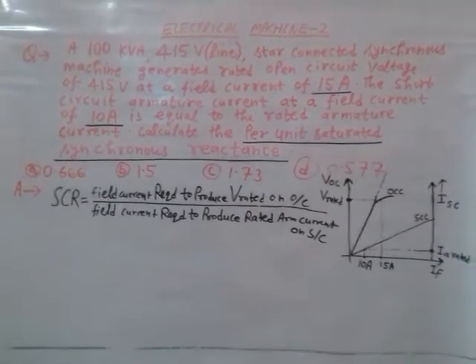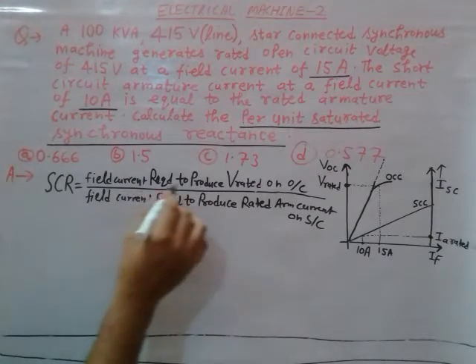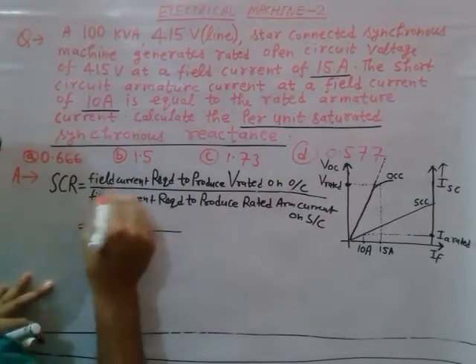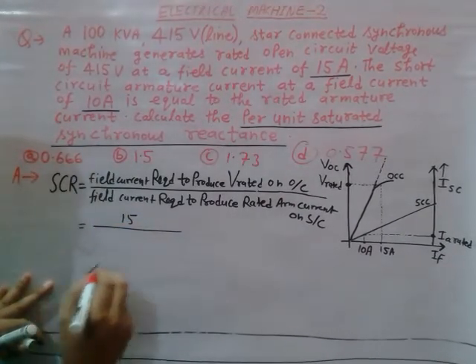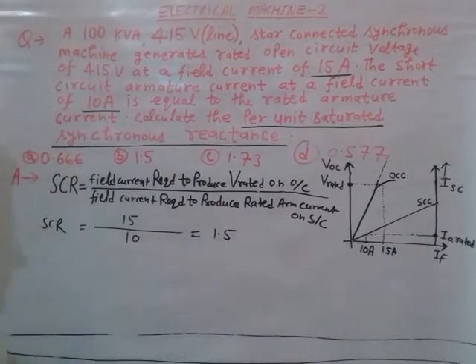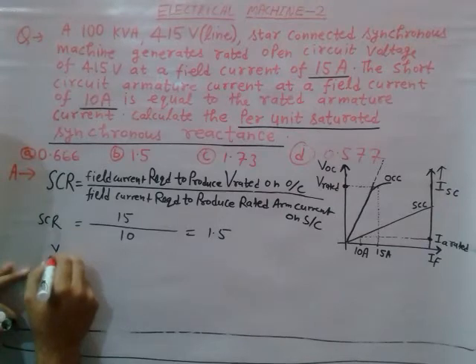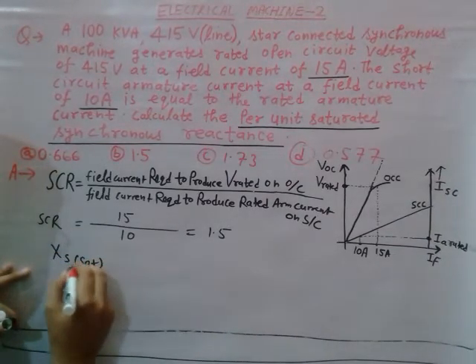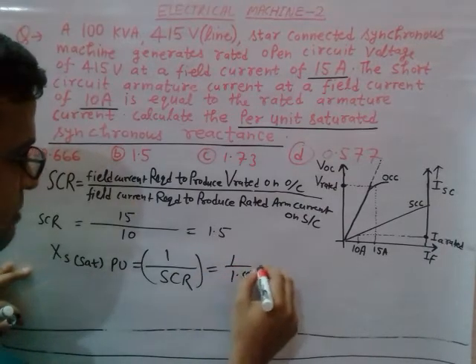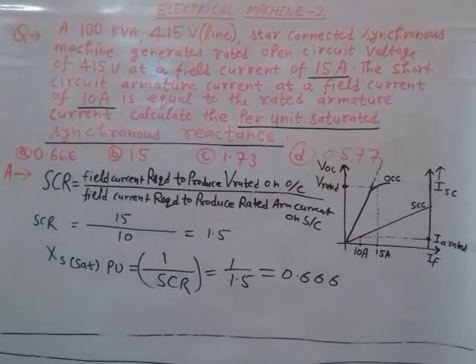SCR, the Short Circuit Ratio, is the ratio of field current required to produce rated voltage on open circuit divided by field current required to produce rated armature current on short circuit. So the numerator is 15 and the denominator is 10, giving SCR = 1.5. The per unit saturated synchronous reactance X_saturated (per unit) is nothing but the inverse of the short circuit ratio: 1 divided by 1.5, which equals 0.666.